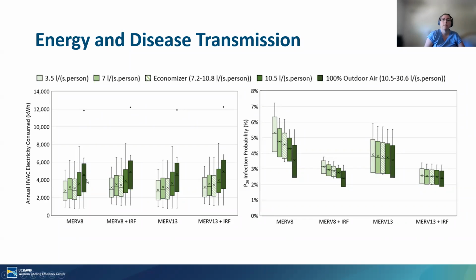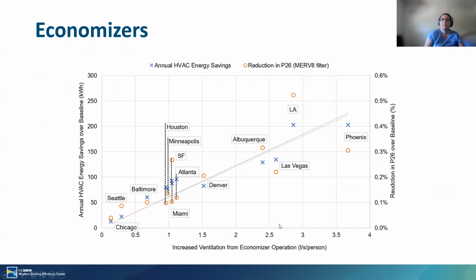And this is just showing what happens with energy as we go through those same parameters. Now, I've talked a little bit about economizers, but I just wanted to bring that up one more time here. So this shows for every city, if we have an economizer from that model, how much increased ventilation above that 7 liters per second per person we would get for the economizer, and then how much energy we would save.